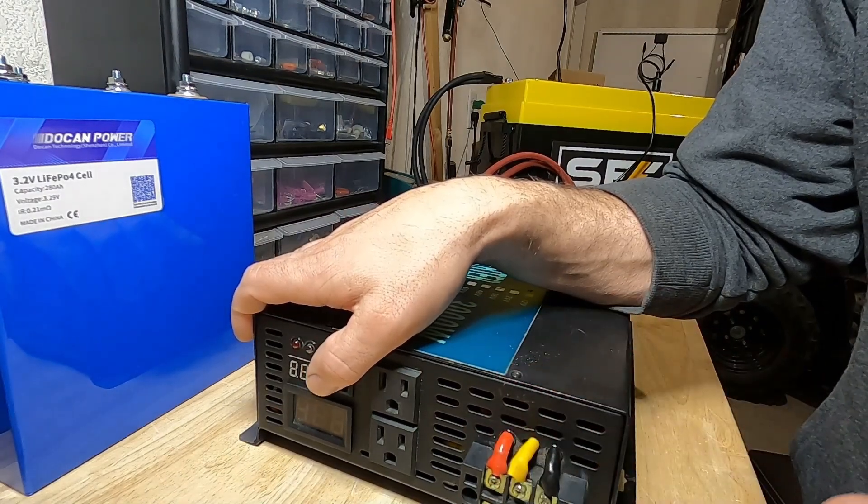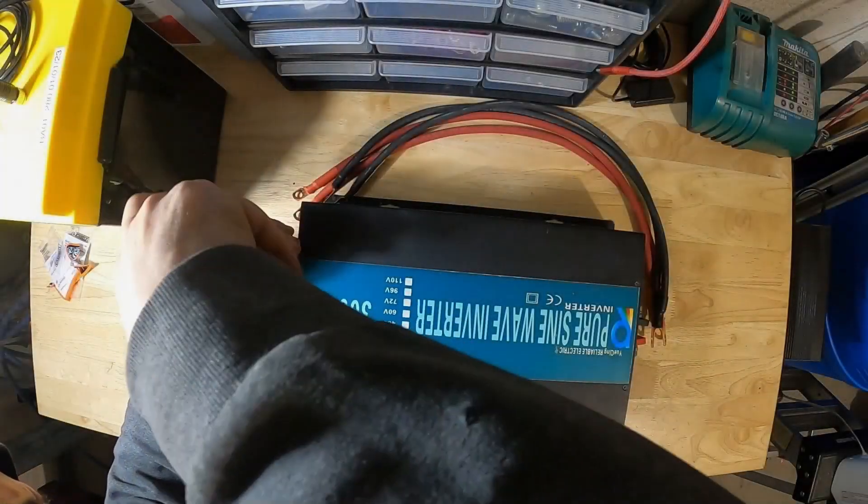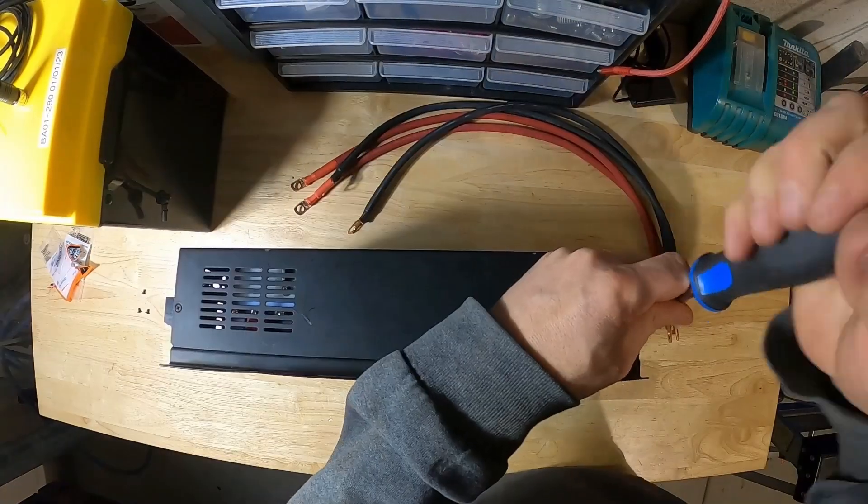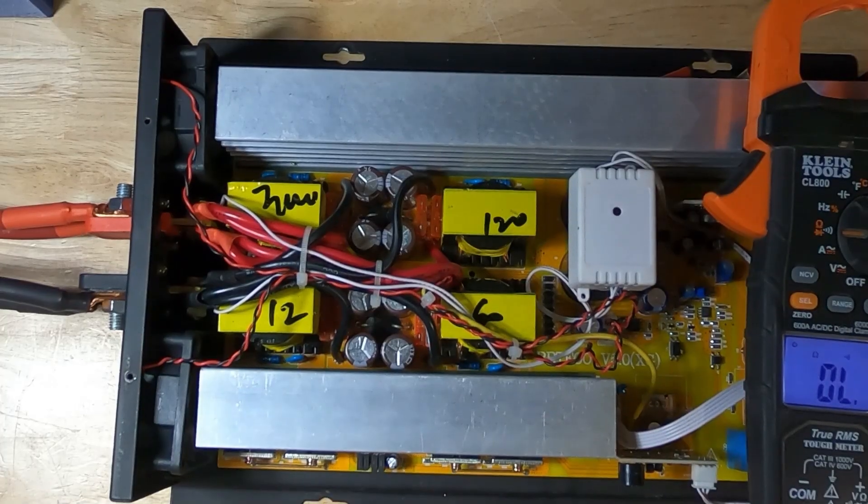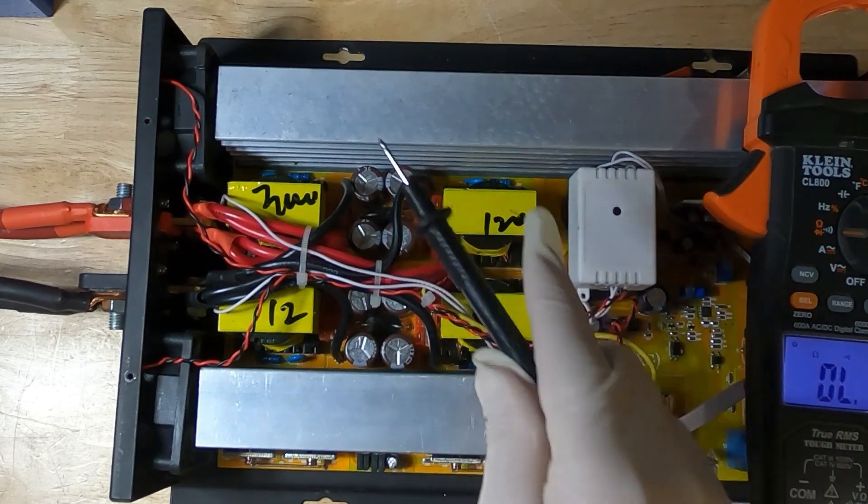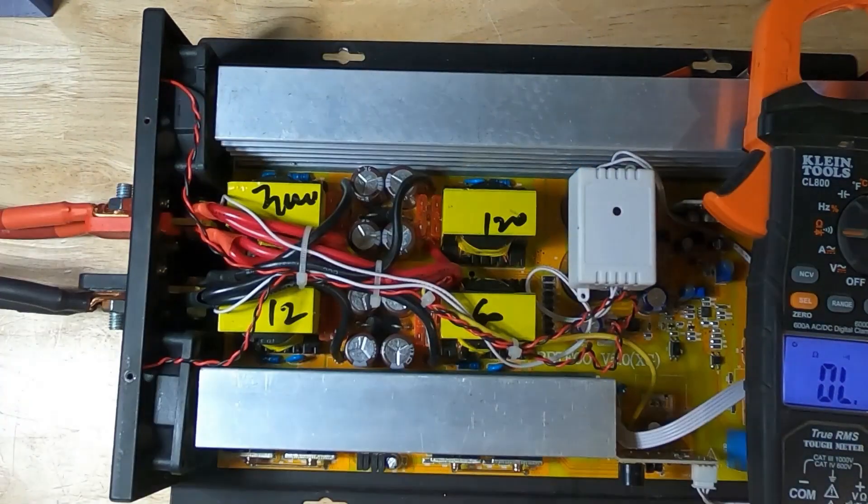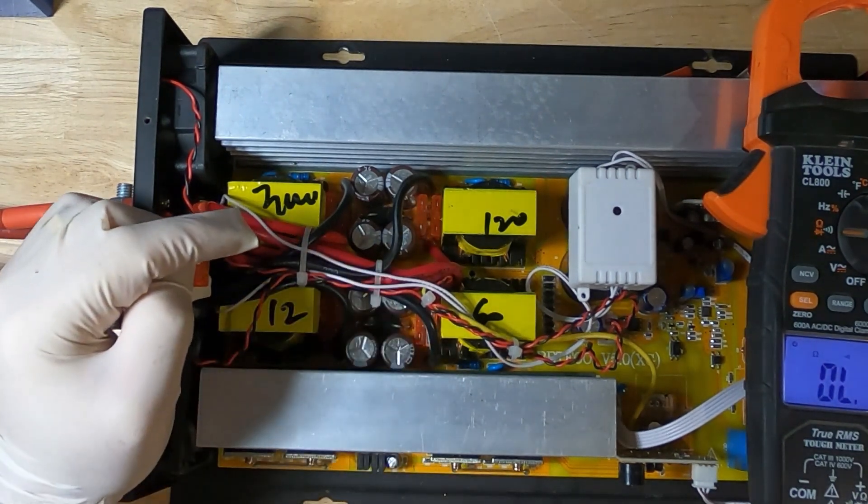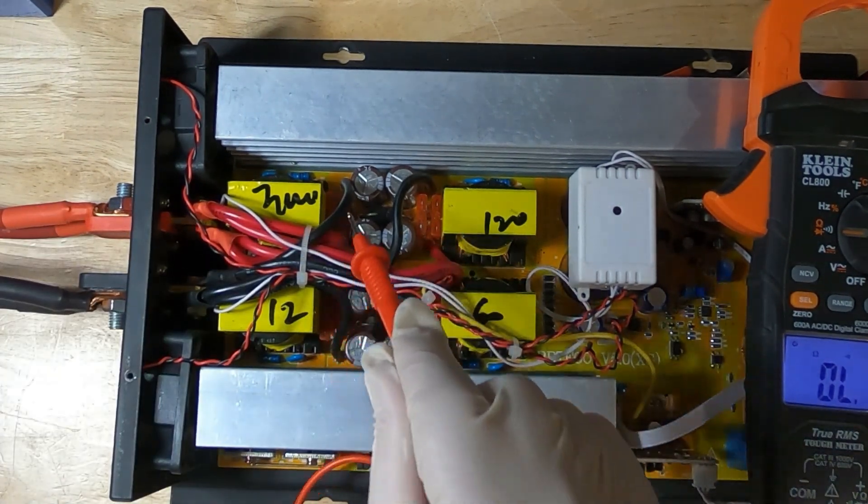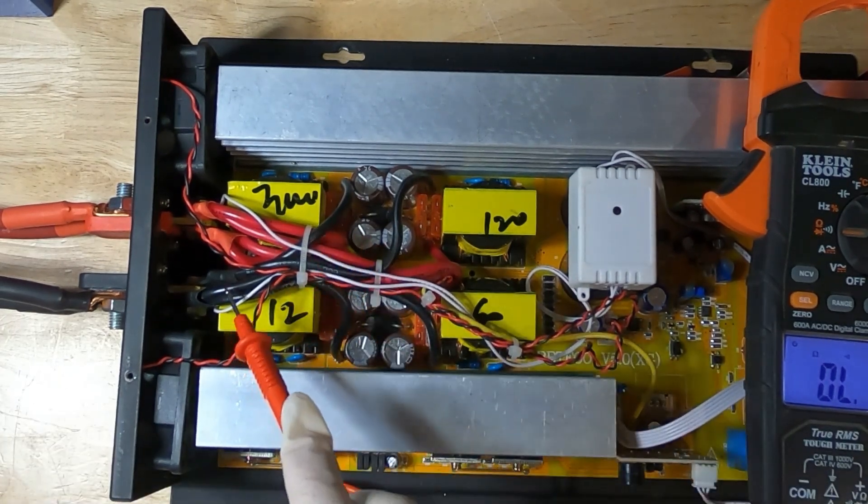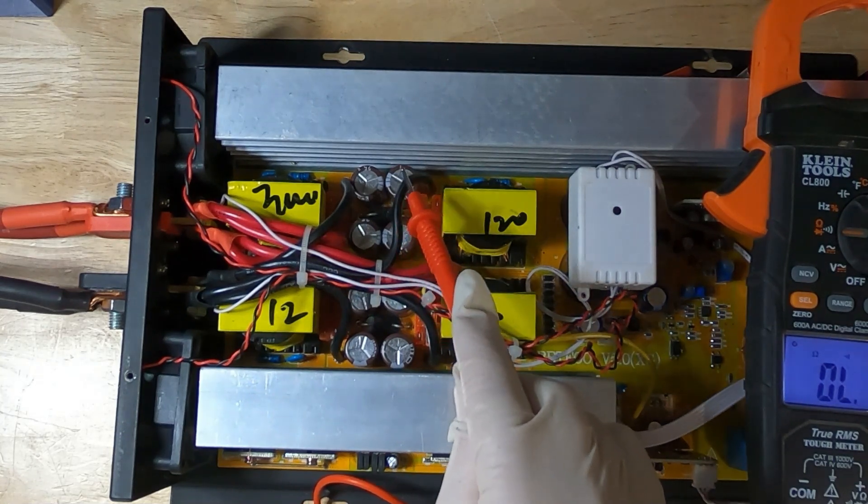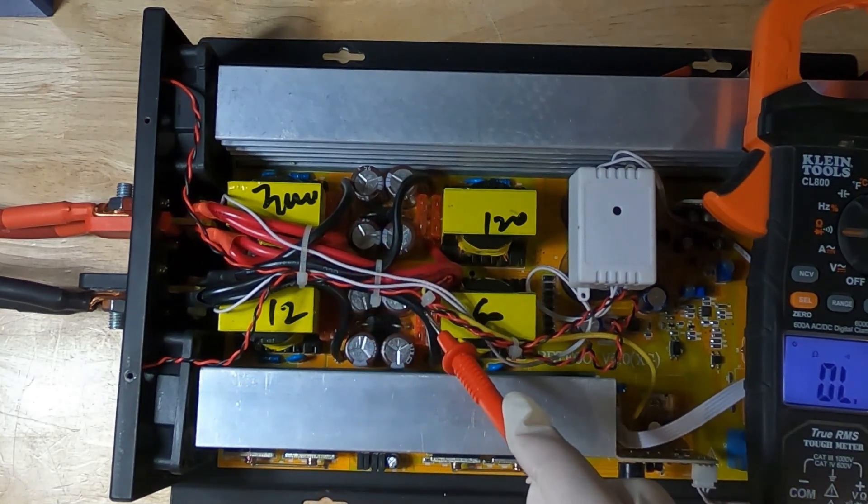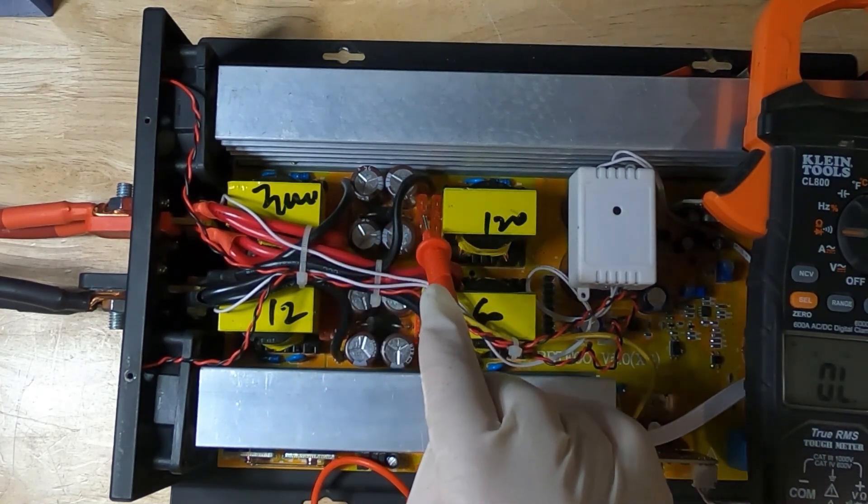I hope I have it zoomed in enough to where you can at least see the fuses down here—these orange fuses. There's a total of eight fuses: two, four, six, eight. You can see there's four black wires, so each wire is 40 amp. Each pair of fuses are actually on a single circuit.